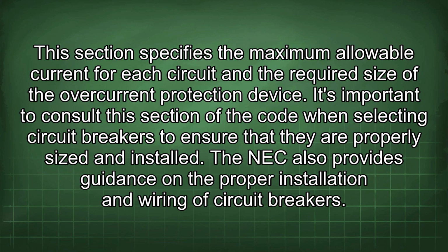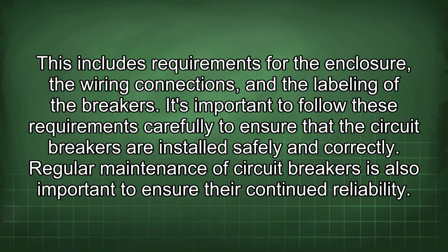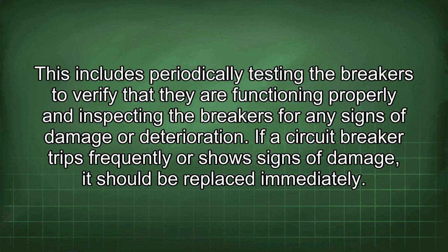The NEC also provides guidance on the proper installation and wiring of circuit breakers. This includes requirements for the enclosure, the wiring connections, and the labeling of the breakers. It's important to follow these requirements carefully to ensure that the circuit breakers are installed safely and correctly. Regular maintenance of circuit breakers is also important to ensure their continued reliability. This includes periodically testing the breakers to verify that they are functioning properly and inspecting the breakers for any signs of damage or deterioration. If a circuit breaker trips frequently or shows signs of damage, it should be replaced immediately.